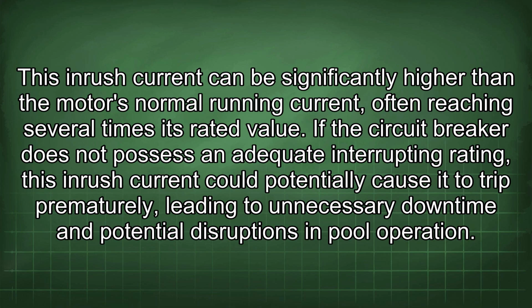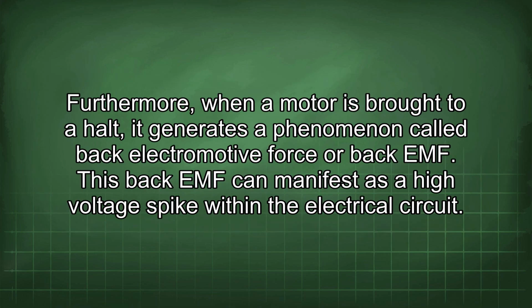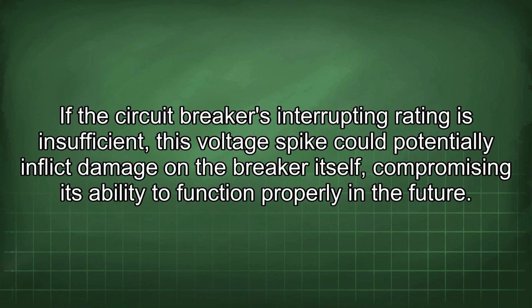If the circuit breaker does not possess an adequate interrupting rating, this inrush current could potentially cause it to trip prematurely, leading to unnecessary downtime and potential disruptions in pool operation. Furthermore, when a motor is brought to a halt, it generates a phenomenon called back electromotive force or back EMF. This back EMF can manifest as a high voltage spike within the electrical circuit. If the circuit breaker's interrupting rating is insufficient, this voltage spike could potentially inflict damage on the breaker itself, compromising its ability to function properly in the future.